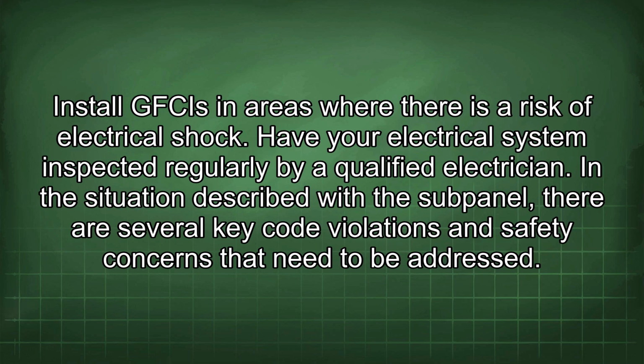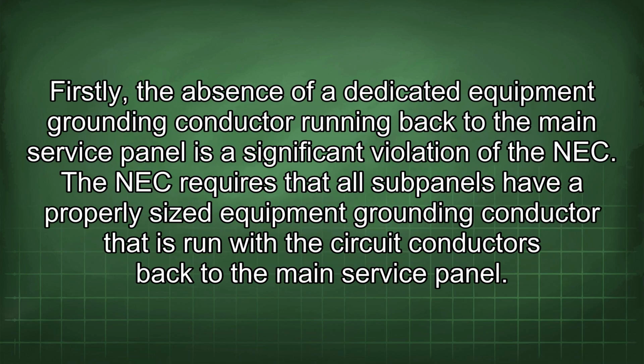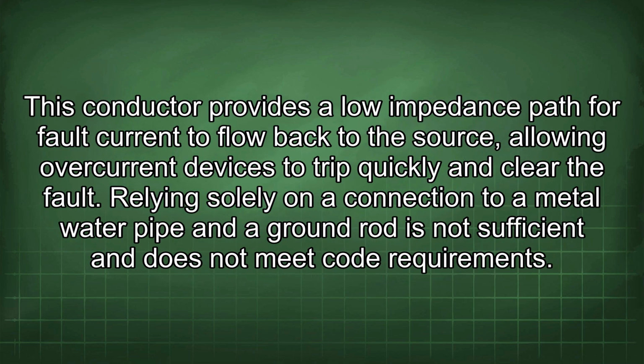In the situation described with the subpanel, there are several key code violations and safety concerns that need to be addressed. Firstly, the absence of a dedicated equipment grounding conductor running back to the main service panel is a significant violation of the NEC. The NEC requires that all subpanels have a properly sized equipment grounding conductor that is run with the circuit conductors back to the main service panel. This conductor provides a low impedance path for fault current to flow back to the source, allowing overcurrent devices to trip quickly and clear the fault.